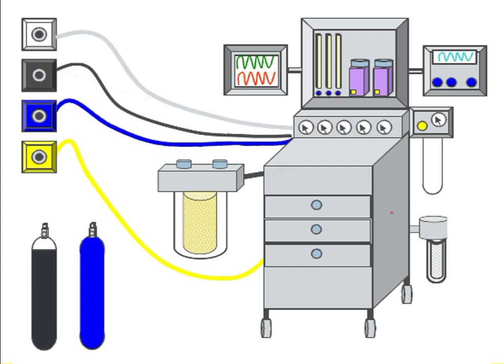You have to supply the patient with different mixtures of gases. The question is: from where do we get these gases? There are many sources to supply the anesthesia machine with gas. The first is the pipelines. If there is a failure in the pipeline system due to misconnection, disconnection, or anything else, we have an emergency backup plan: the E-cylinders, or emergency cylinders.